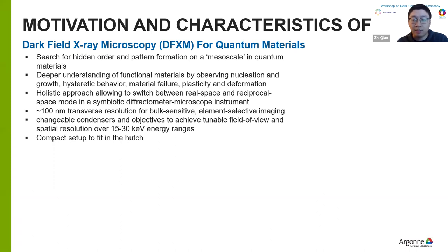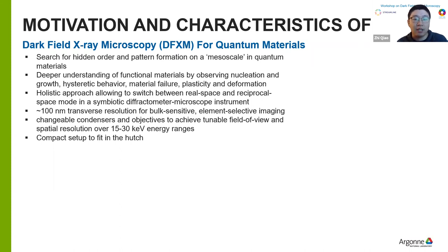For this dark field x-ray microscope, we want to easily switch between the real space and reciprocal space modes in the diffractometer instrument, and we want to get a spatial resolution around 100 nanometers from bulk-sensitive and element-selective imaging. Besides high resolution, we also want a zooming capability to switch from high spatial resolution mode to large field of view modes over a 15 to 30 keV energy range. Finally, we want the whole setup to be compact to fit in a roughly 4-meter hutch.